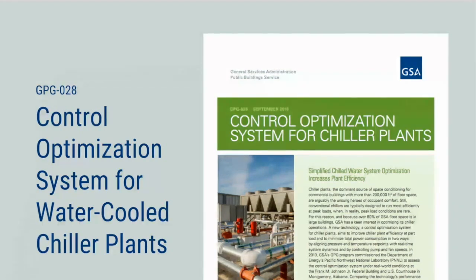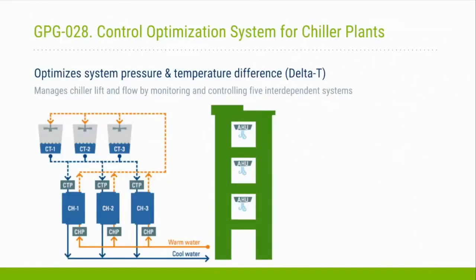On the current slide, there's just a short description of some of the challenges that are being faced by chilled water plants in commercial buildings. This slide shows typical commercial building optimization issues that are currently encountered: the dance, if you will, the synchronization of multiple components, towers, tower fans, condenser water pumps, chilled water pumps, and then it gets even more complex if your system is a primary, secondary, where you have pumping systems that are pumping out to the buildings. And this is a very simplified diagram of the site at Montgomery, Alabama that we're going to be talking about.